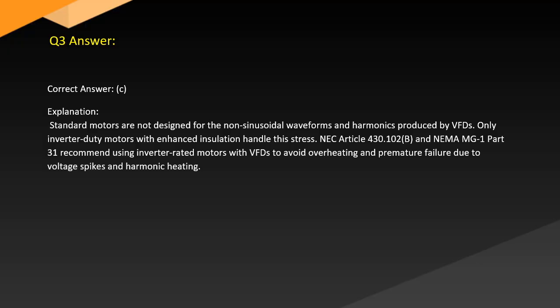Answer. Correct answer: C. Explanation. Standard motors are not designed for the non-sinusoidal waveforms and harmonics produced by VFDs. Only inverter duty motors with enhanced insulation handle this stress. NEC Article 430.102(b) and NEMA MG1 Part 31 recommend using inverter-rated motors with VFDs to avoid overheating and premature failure due to voltage spikes and harmonic heating.